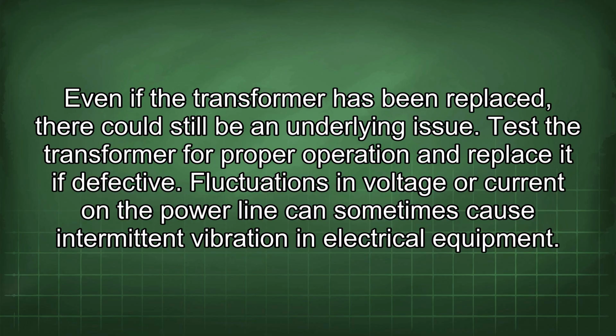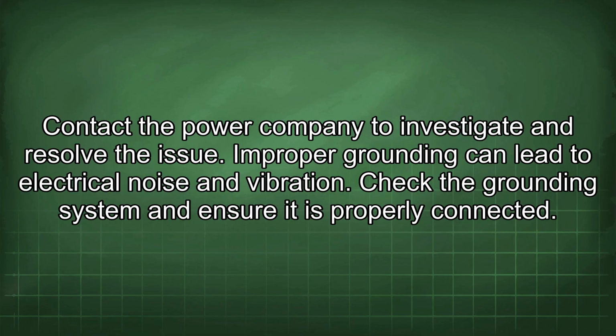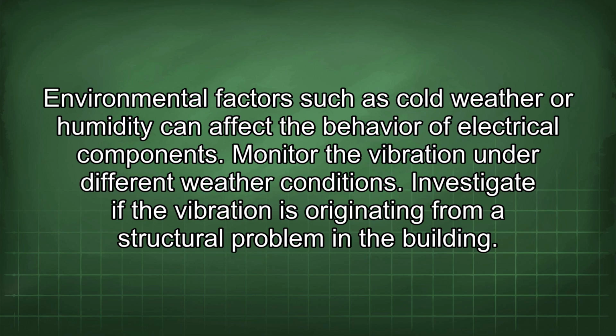Even if the transformer has been replaced, there could still be an underlying issue. Test the transformer for proper operation or replace it if defective. Fluctuations in voltage or current on the power line can sometimes cause intermittent vibration in electrical equipment. Contact the power company to investigate and resolve the issue. Improper grounding can lead to electrical noise and vibration. Check the grounding system and ensure it is properly connected. Environmental factors such as cold weather or humidity can affect the behavior of electrical components. Monitor the vibration under different weather conditions.